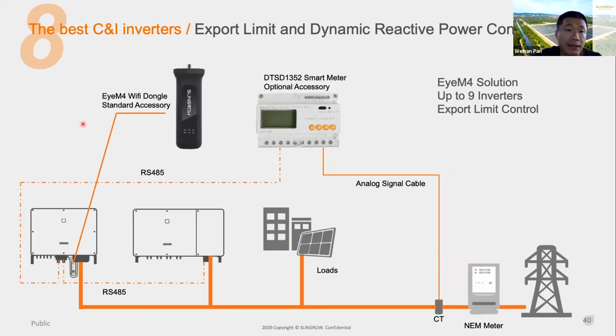And next one is export limit and dynamic reactive power control. When a customer purchases our C&I range inverter, there will be an EyeM4 Wi-Fi dongle. It's a standard accessory for communication and power control. And the EyeM4 dongle can support up to 9 inverters for this sort of application. You only need to install it on one master inverter and then daisy chain the rest of them. And the dongle will coordinate with our smart meter so as to do the export limit and the dynamic reactive power control.